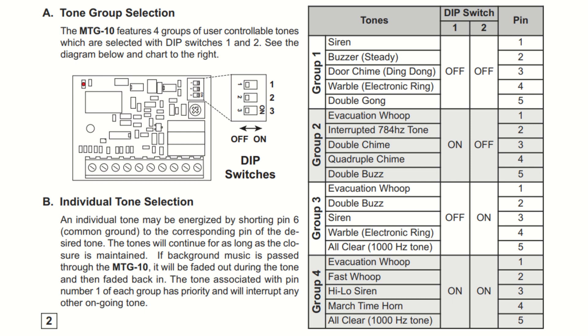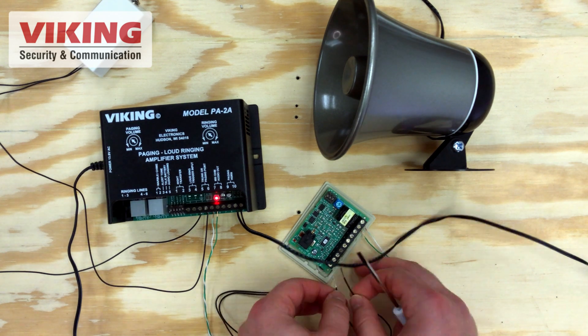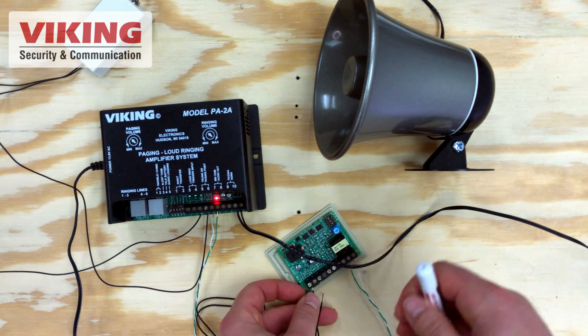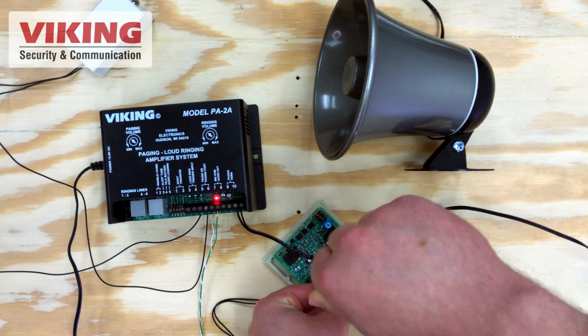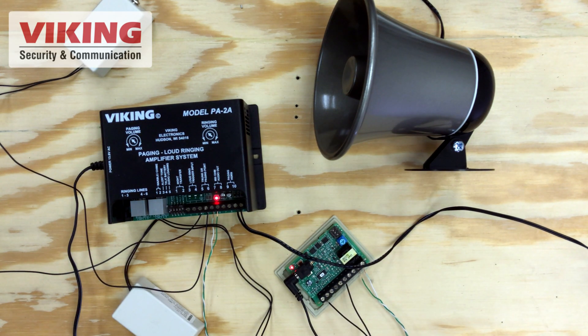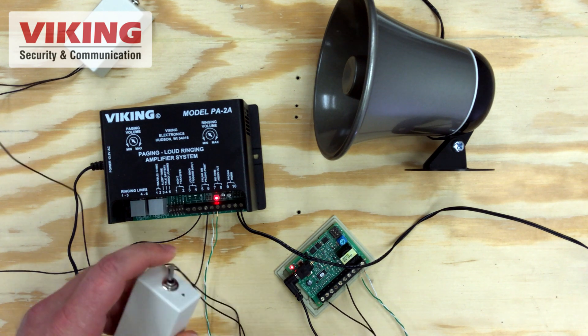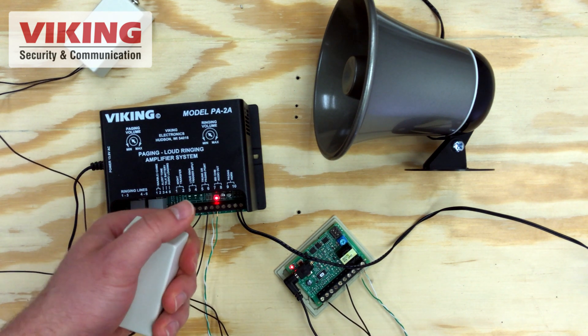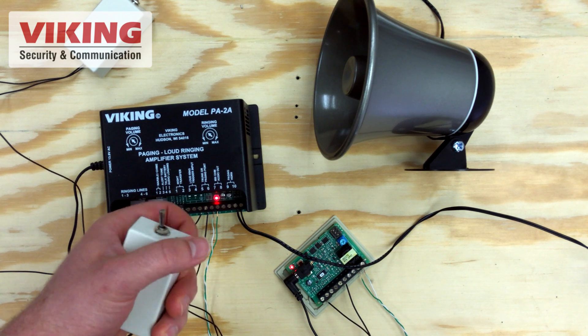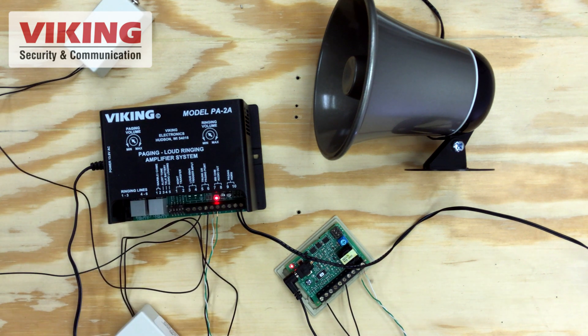Use DIP switches one and two on the MTG-10 to select from your different banks of tones, and then wire the normally open contact between the tone select pin one through five and pin six, which is common. A contact closure across these pins will produce an audio tone. This tone remains active for the duration of the contact closure.